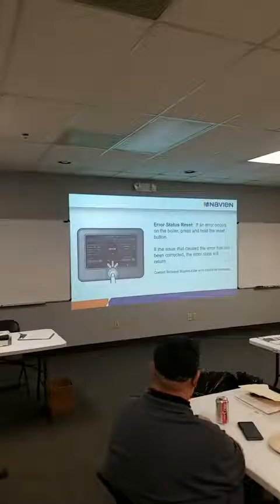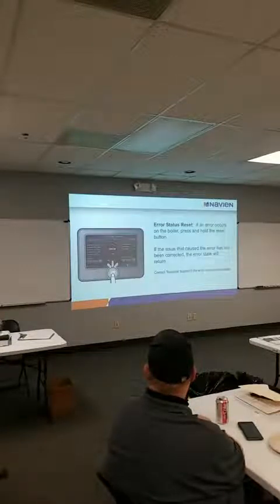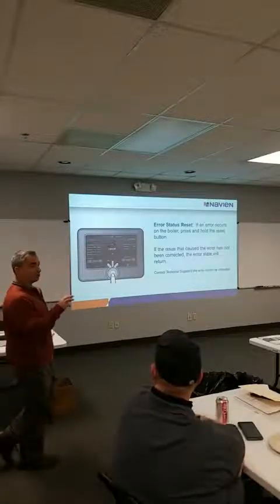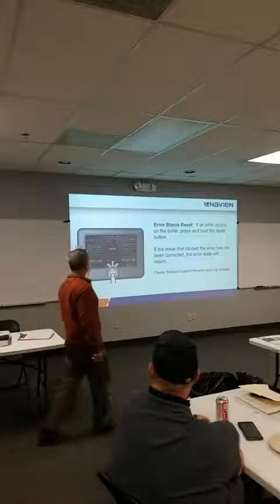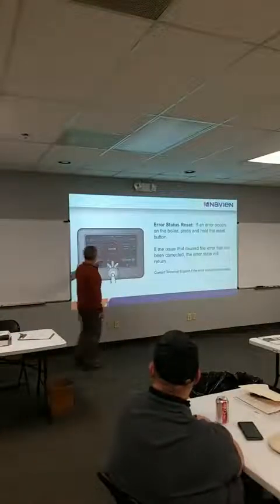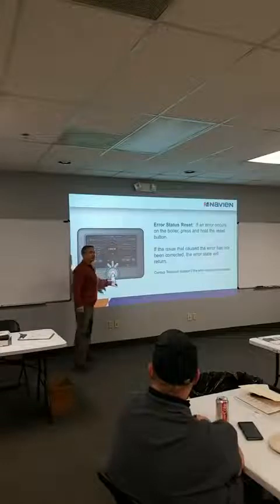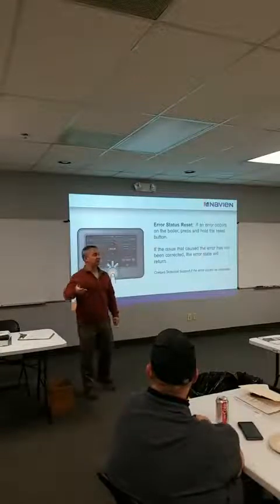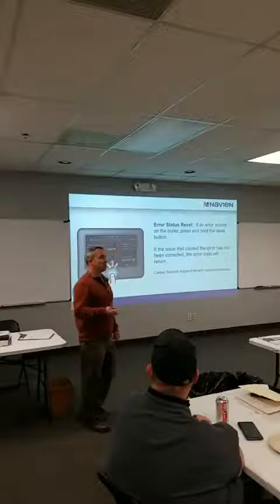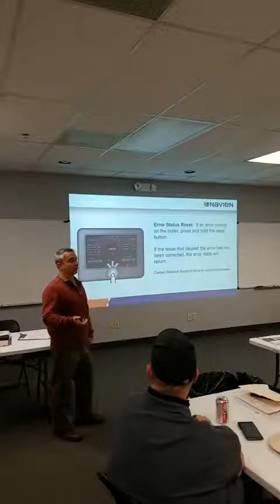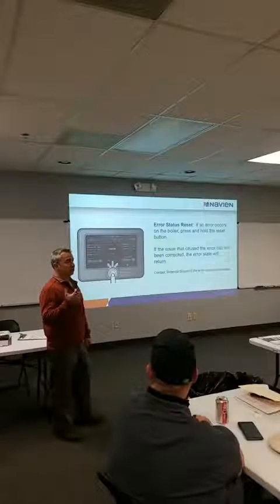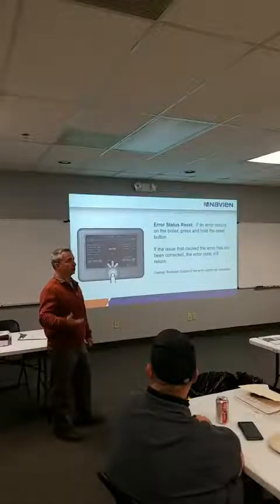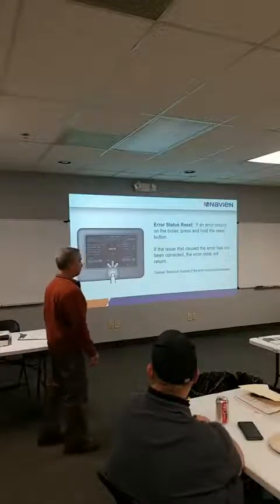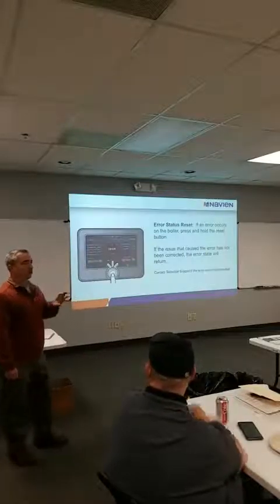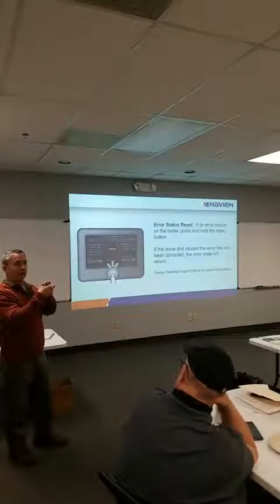So, all of our units store up to 12 error codes in the system. The keypads do different things when errors pop up, but for the most part, the error's gonna pop up. It's gonna give you an error code, and then you just hit the button to reset that code out, and it'll store it, and it'll try to refire the system. There's a couple gas codes and a couple venting codes that are hard lockouts that won't restart the system unless you power it down and power it back up, then it'll try to go into fire at that point. The NFB and the combi control flashes red, and it tells you that error code.